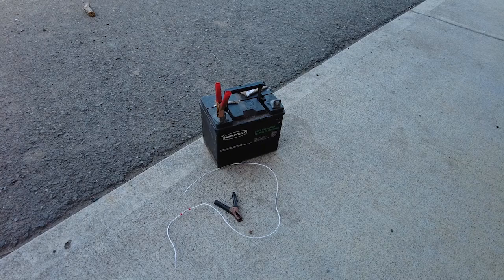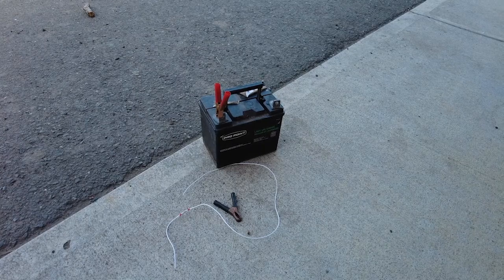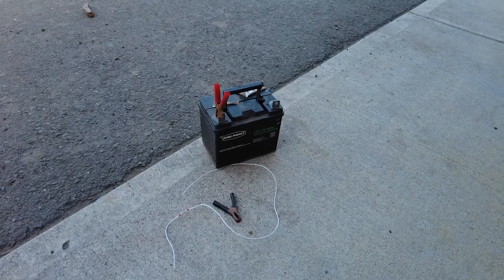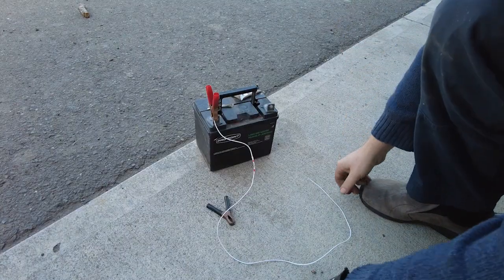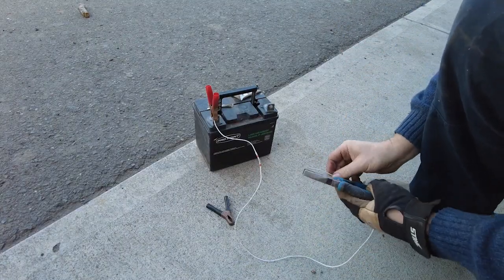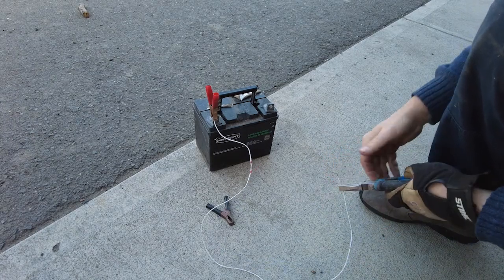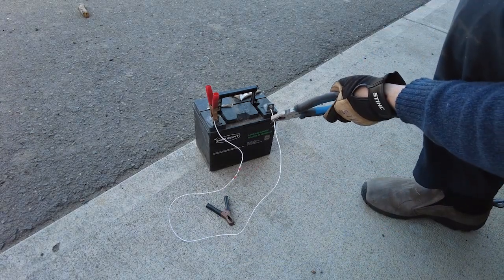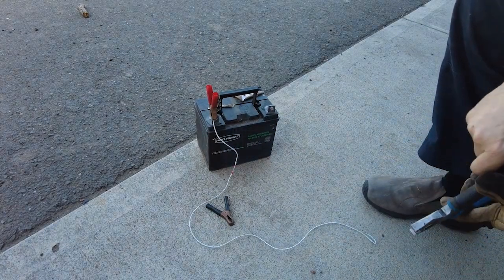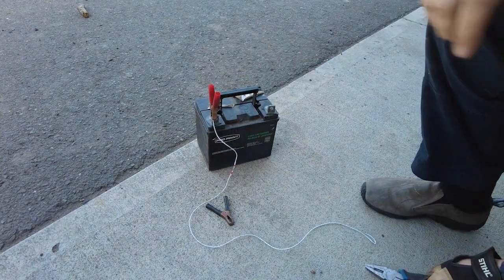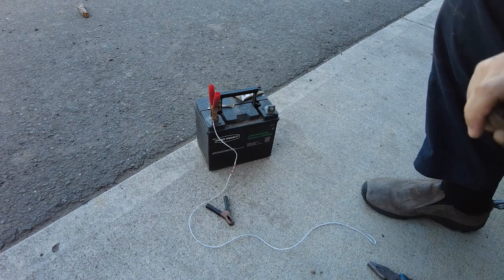So we're going to test it anyway though, just for fun. So we're going to dead short this wire, this 18 gauge wire with that connector, to that battery and see what happens. All right, so we're going to use pliers because this wire is going to get really hot in a big hurry and it's going to want to weld itself to that negative terminal. Sure enough, so what was that, a quarter second and the whole wire smoked.